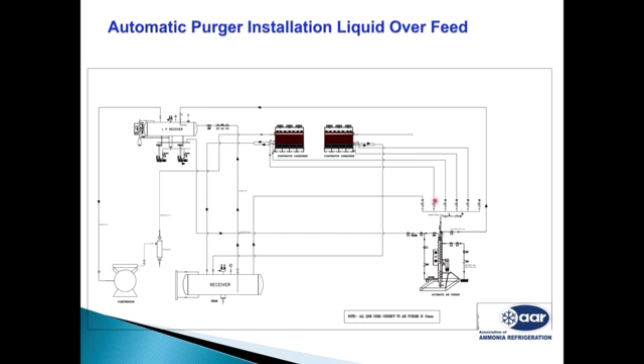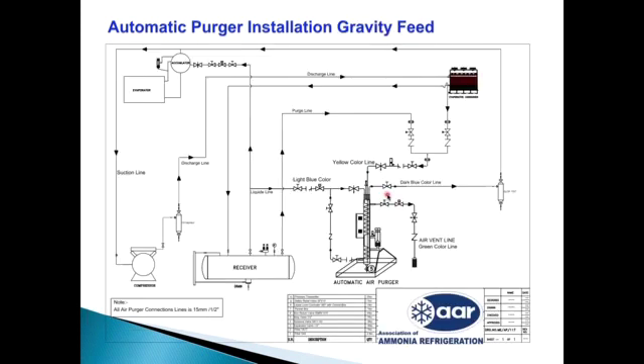When the foul gases come in contact with this coil, they condense, and if there is ammonia, it becomes liquid and is fed back into the system. If non-condensable gases accumulate, there is a control system here which senses the non-condensable gases and vents them into the water. This drawing is for a pump recirculation or LP vessel system or forced liquid feed system. And this drawing is for the gravity fed system. We can install air purgers in a gravity fed system also. We can use one common slop pot, or we can connect to the available accumulators in the system.